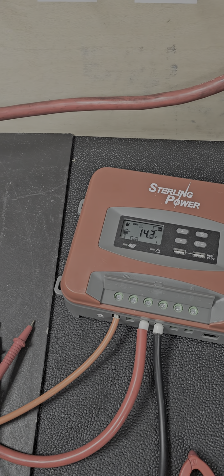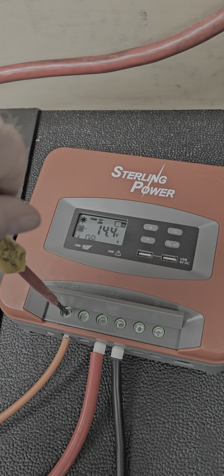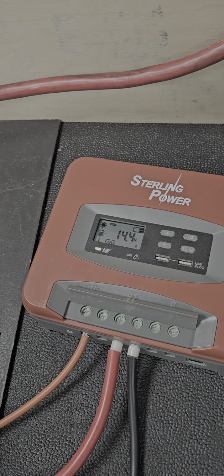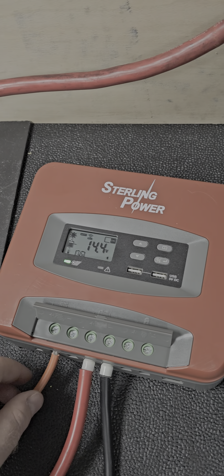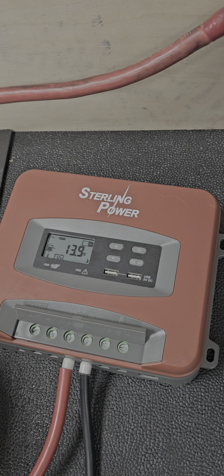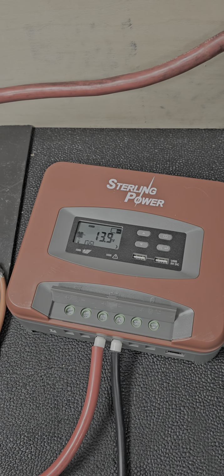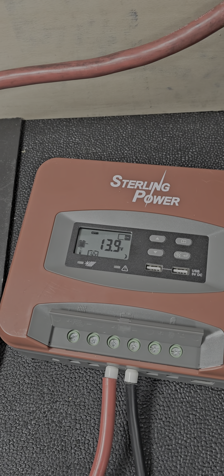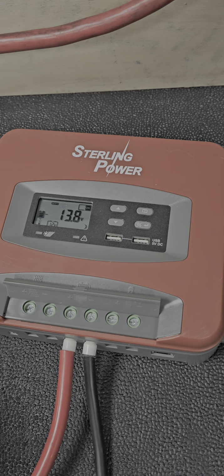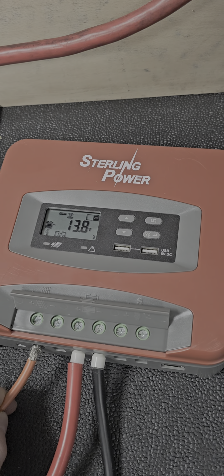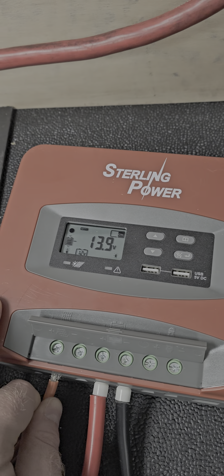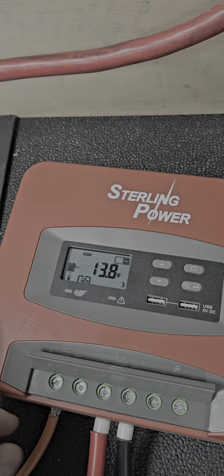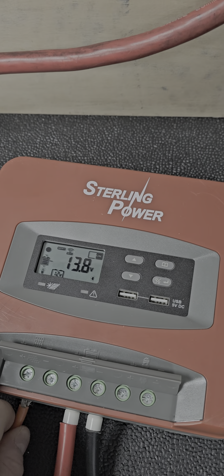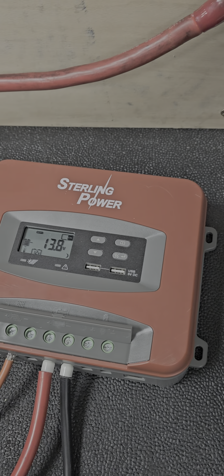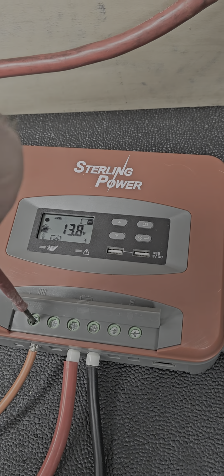Likewise with the 12 volt, if I was to remove the feed - with an isolation switch, or since these are lithium batteries I can just turn it off on my phone - all that happens is the charging stops because there's no pressure or current flow, and the unit just sits there with the battery voltage at 13.9 volts. Then if I reconnect solar back into it, there's a little spark because we're at 51 volts, and the solar shall begin again - you can see it's just recognised the solar feed there, and we should be back charging in a moment. Let me just make sure that's nice and tight.